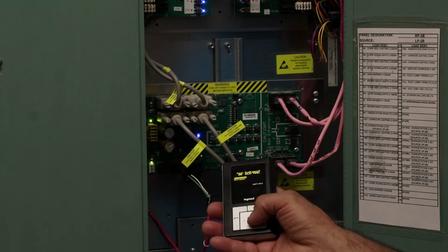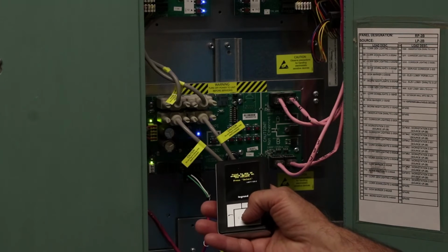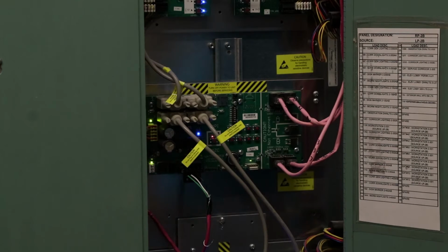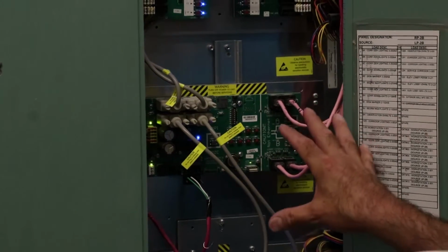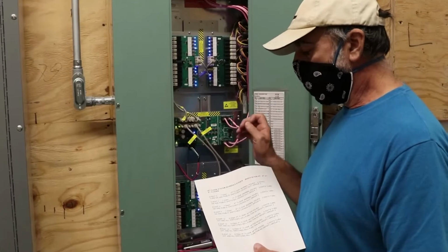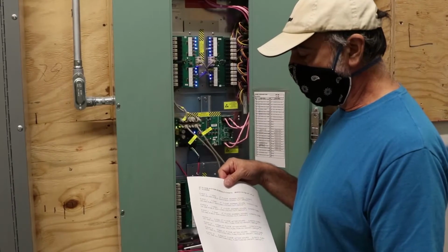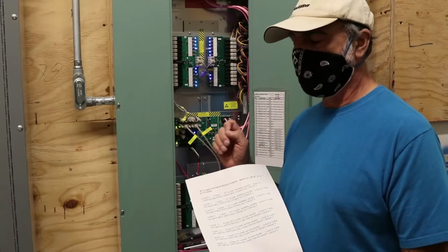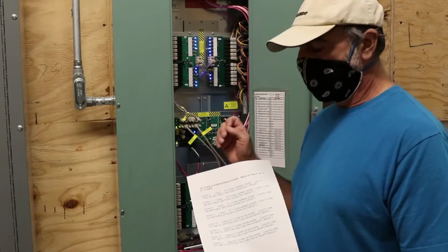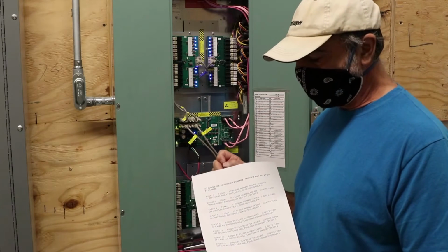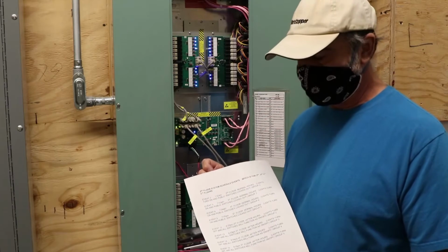First thing that comes up is schedules, so I'm going to press that. And the way the scheduling works is each schedule is actually, in its language, an event. So the way I numbered them is starting with event 2, that represents the second floor on. Event 3 is the third floor on. Event 4 is the fourth floor on, and event 5 is the fifth floor on.